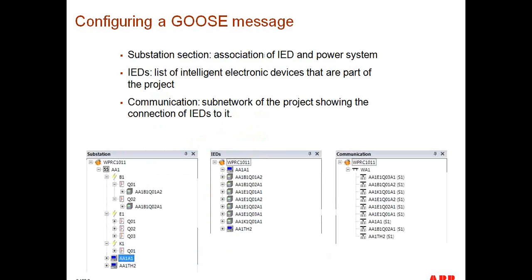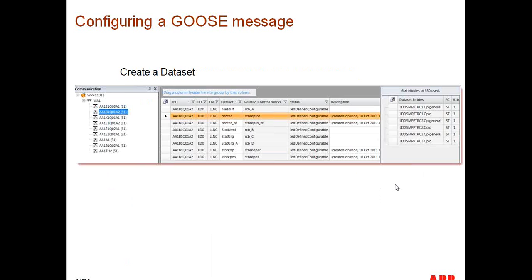So when we look at the configuration of a GOOSE message, depending on the software that's being used, you could have a view of your substation, which essentially gives you a representation of your individual relay and its connection to the system, substation, voltage level, and then the particular bay this relay is associated with. Then you could also have a view of just all the relays that are part of the project. And then you also have something that's called the communications section. You can have one or multiple communication networks. The communication section describes which device or which IED is connected to which network. If you have time servers, if you have HMIs, all of this is documented inside this. So IP addresses, IED names and IP addresses and so on. It's all part of this file structure.